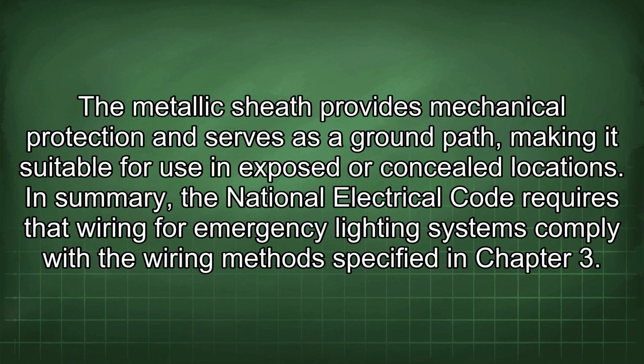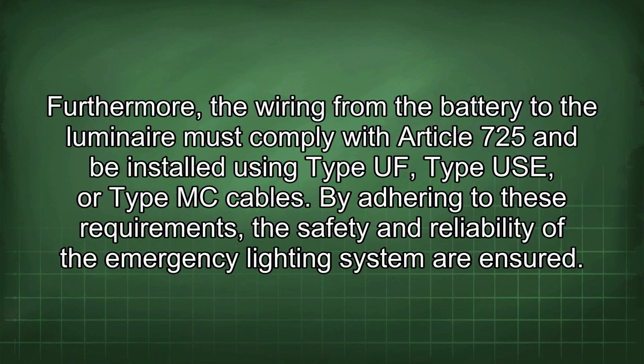concealed locations. In summary, the National Electrical Code requires that wiring for emergency lighting systems comply with the wiring methods specified in Chapter 3. Furthermore, the wiring from the battery to the luminaire must comply with Article 725 and be installed using Type UF, Type USE, or Type MC cables. By adhering to these requirements, the safety and reliability of the emergency lighting system are ensured.